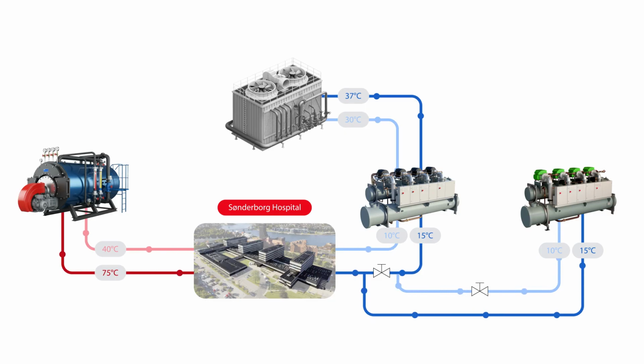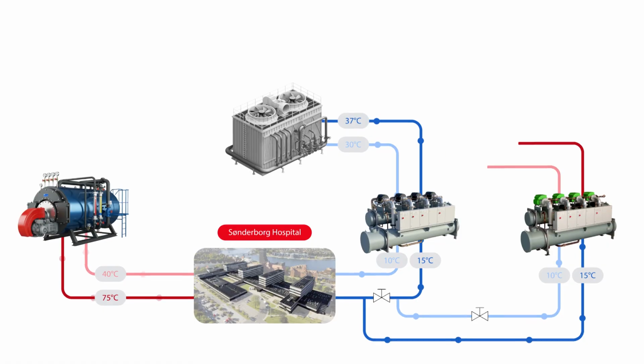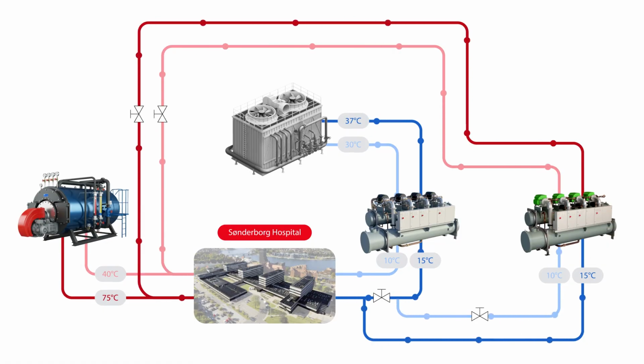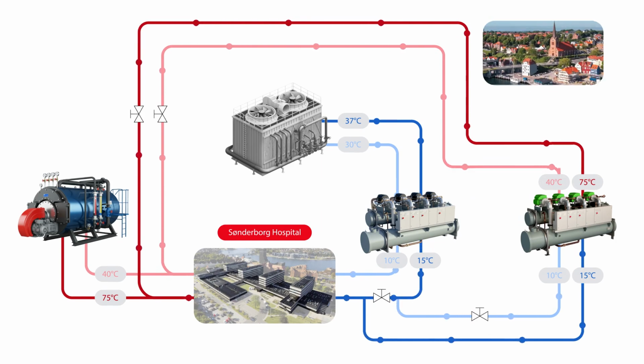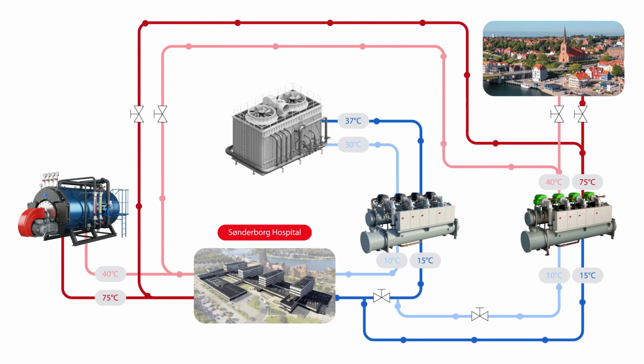Instead of discarding the extracted heat, that energy now becomes the heat source. The heat pump raises water to 75 degrees Celsius for the hospital's space heating and domestic hot water. Surplus heat is fed to the district grid, and extra heat is drawn when demand exceeds pump capacity.